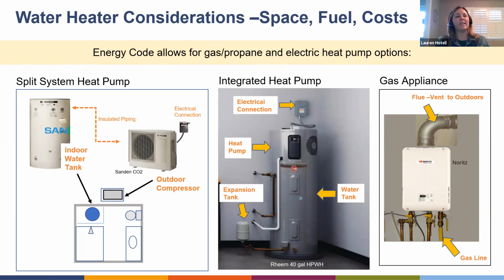Do tankless heat pump water heaters exist? No, they do not. The heat pump water heaters need a tank of water. They need that tank. They depend on something called stratification, where they want the bottom of the tank to have the cold water and the top of the tank to have the hot water.